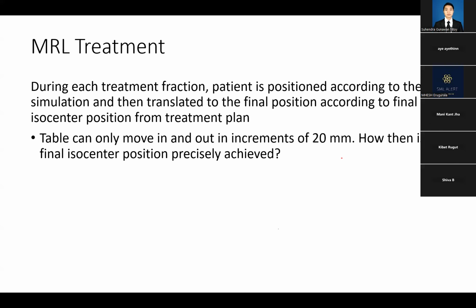So during each treatment fraction, another interesting thing, at least for the Unity, I don't know for the Versa if this is the case, but at least for the Unity, one really unique thing is that the couch only moves in and out. You set the isocenter and you set the index on the couch where you want it to be at isocenter. So if you lay the patient down and the target is at 20, you'll send the couch to 20 at the beam isocenter. But there's no lateral movement of the couch, there's no up and down movement of the couch, and there's no roll or yaw or pitch of the couch. So this is unusual because in conventional treatments, that's what allows you to match your geometry of the day to your simulation geometry. But we don't have that in the Unity.